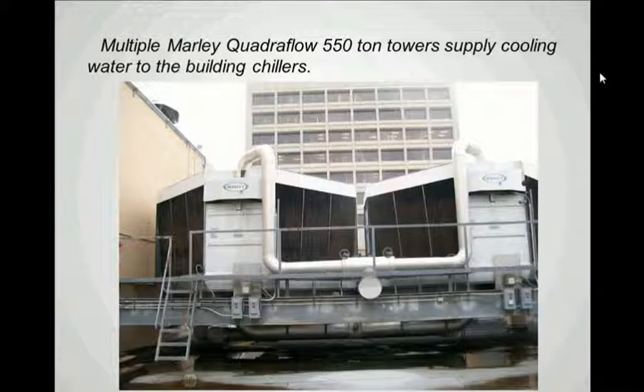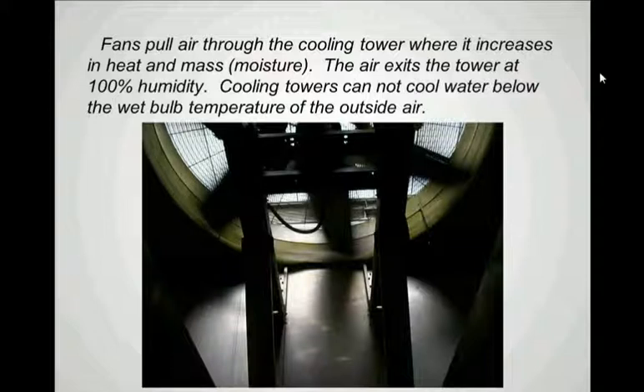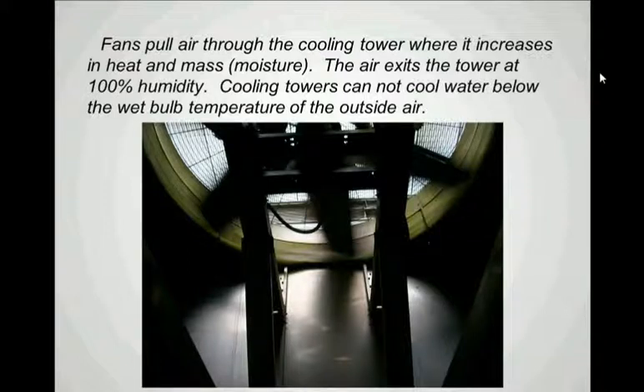Now if we look inside the cooling tower, we get a better view of the fan. We're inside the cooling tower looking up at the fan. These large fans pull air through the cooling tower, where in that process water is evaporated. That water that is evaporated passes into the air to increase the moisture content of the air that exits the cooling tower. In fact, the air that exits the tower is at about 100% humidity, meaning it's saturated with water. In this process of evaporation, the bulk of the cooling water that remains — that's not evaporated — is cooled.